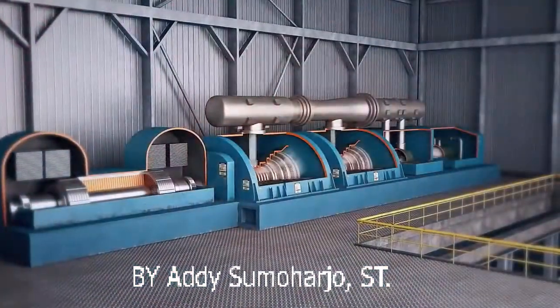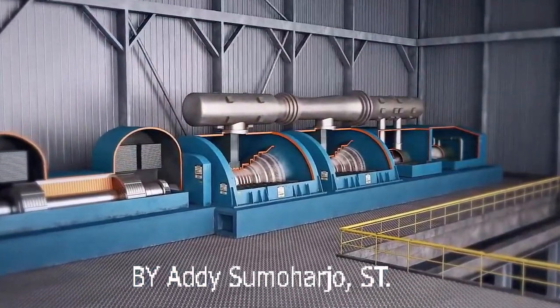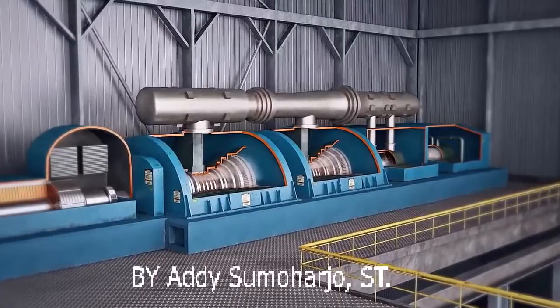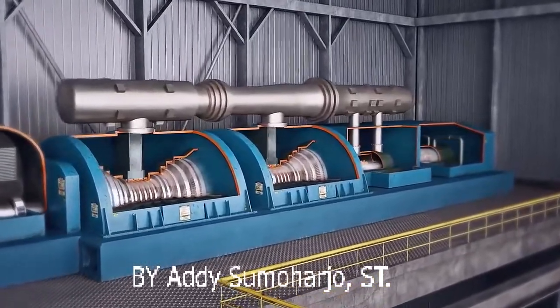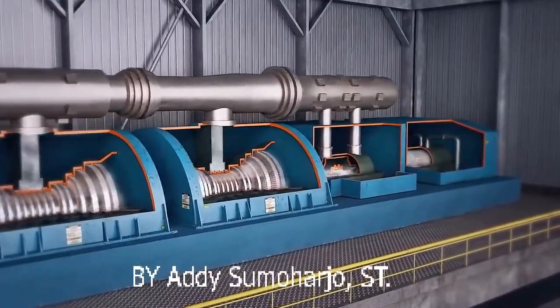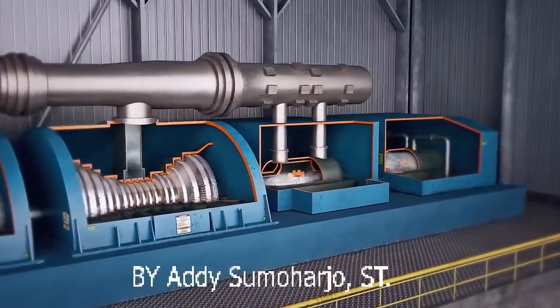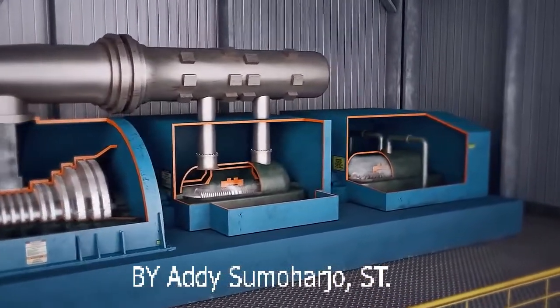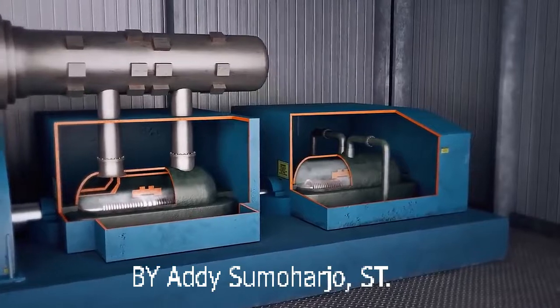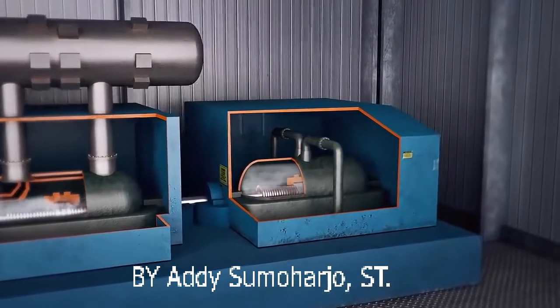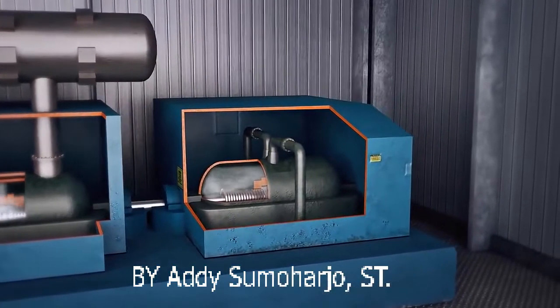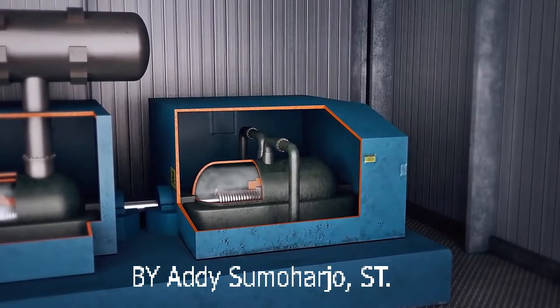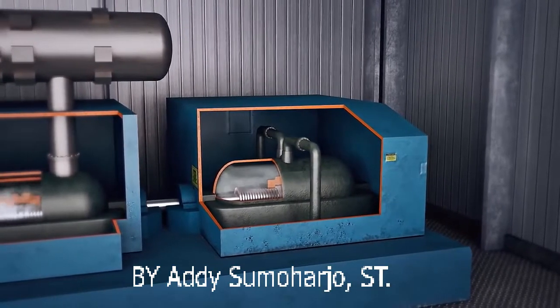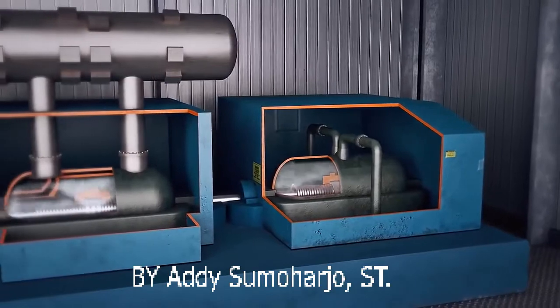Superheated steam from the boiler, which is approximately 2400 psi and 1000 degrees, travels to the high-pressure section of the turbine, where it creates the force that turns the turbine shaft. This process causes the steam to lose temperature and pressure, so it must be sent back to the boiler to be reheated to 1000 degrees. After reheating, the steam returns to the intermediate turbine and continues through the crossover into the low-pressure turbines.